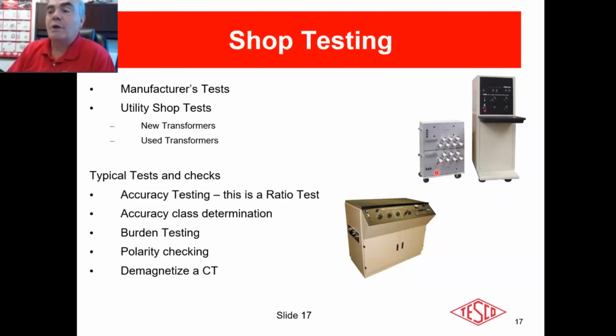And all you're really doing is you're taking your transformer under test, which might be here, you're hooking it up, and the loading transformer is feeding the precision and your transformer under test, and you're comparing what the precision is outputting and what your transformer under test is outputting. Compare the two, that's your accuracy, okay? Pretty basic, all right? Same thing in your, this is a KCTS, this is your current transformer test system.